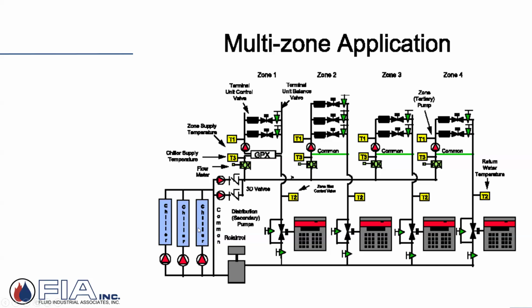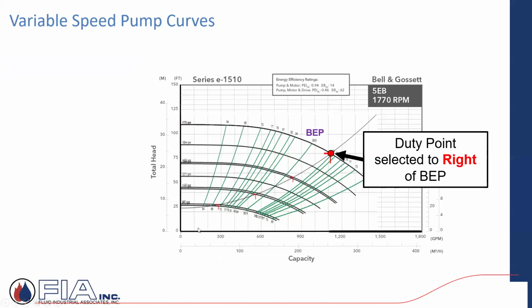And then I have, again, drives for both the distribution that's feeding the buildings depending upon the load of the control valve. And then I might have, as individual terminal control valves are changing or closing, controlling the variable speed of the tertiary pumps. So, it can be a really fairly complex system, a built-up system. And what they're trying to show here is when you're picking the pump, duty point.